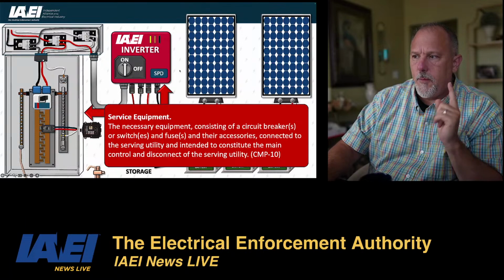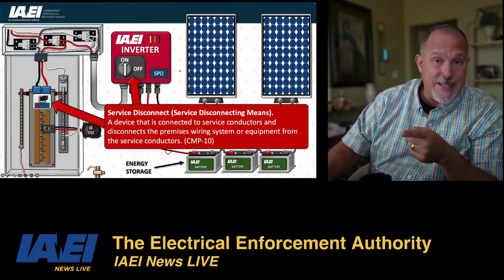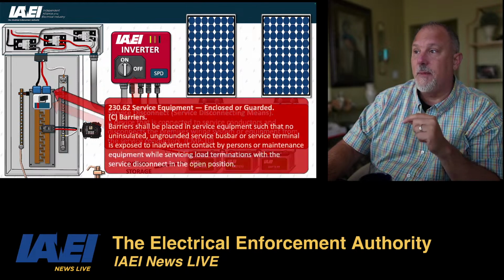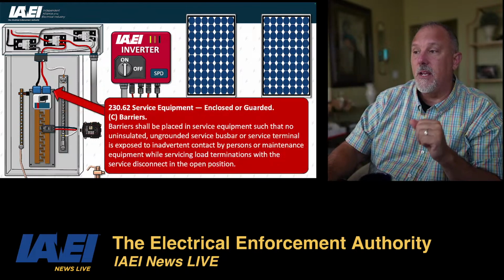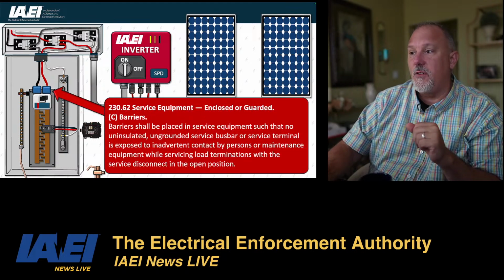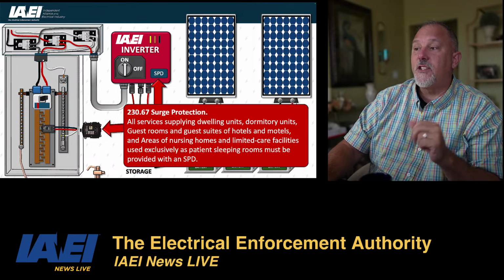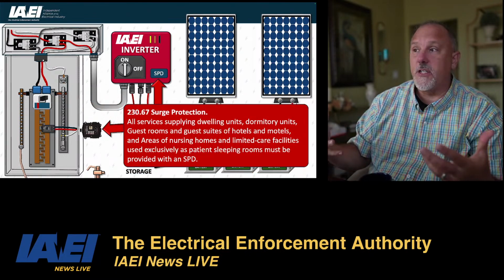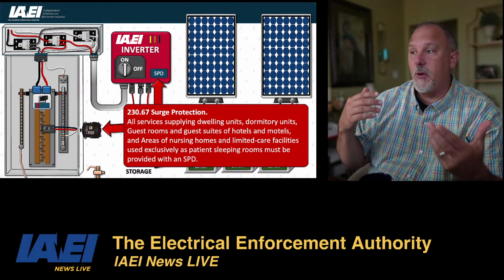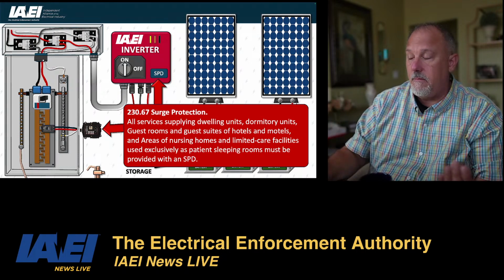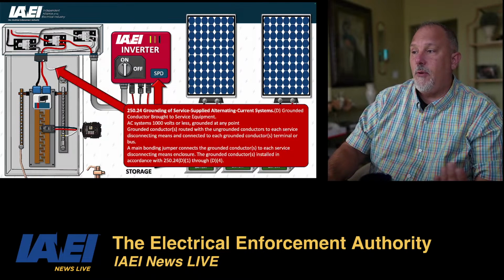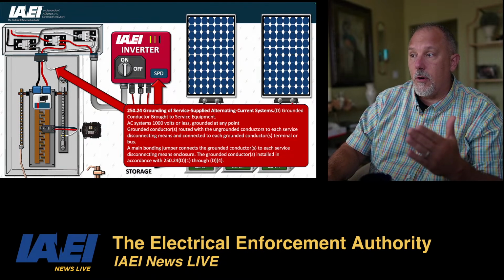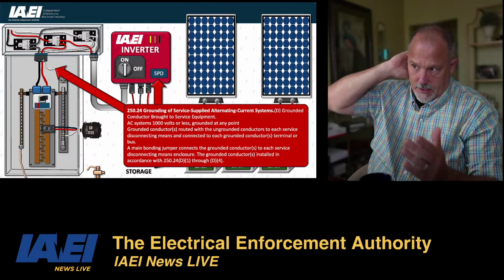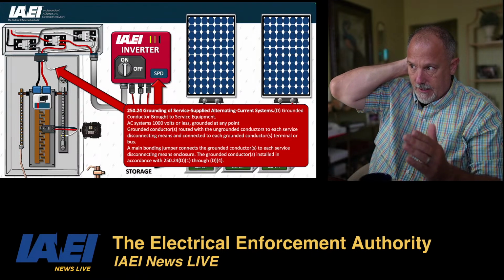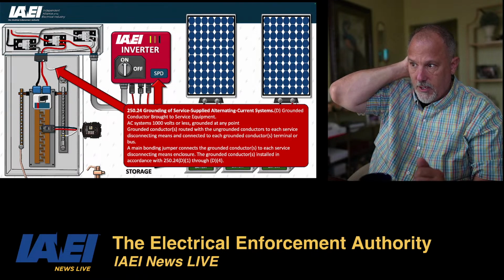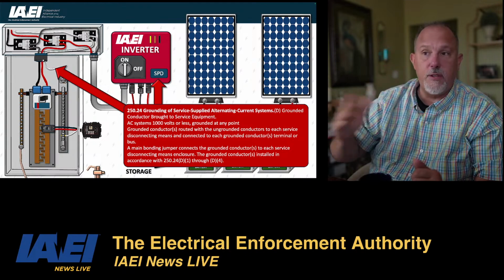That is service equipment. We already talked about that. That's a service disconnecting means. We already talked about both of those are service disconnecting means. We have the line side barriers as part of 230.62. Surge protection is required in service equipment, so that's a requirement as per 230.67. And then you have the 250.24 grounding that you need to have. You need to route your grounded conductor to that equipment.